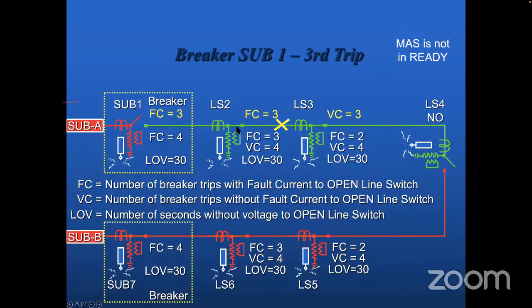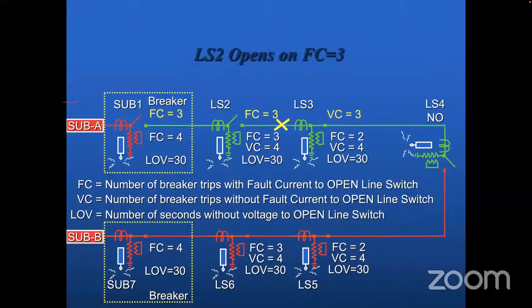So this switch is not a breaker - only a breaker can open when high current is flowing through it. So this switch cannot open because it cannot break the fault current. But currently there is no current - it's de-energized, this green line is de-energized. So now at FC3, what happens is it has to open it - a local, intelligent, autonomous decision that at FC3 it opens up.